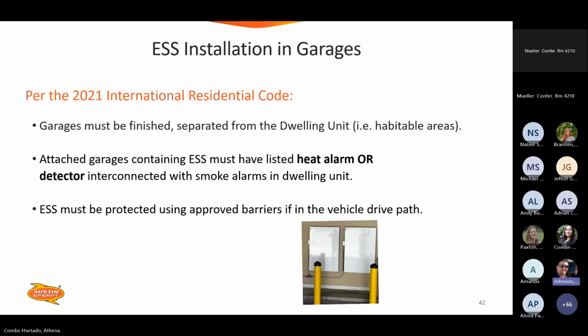Attached garages containing ESS must have a listed heat alarm or heat detector interconnected with smoke alarms in the dwelling unit. And if it is in the straightforward drive path, not on the sides of the garage, the straightforward drive path, meaning they can easily pull in and not be paying a smidgen of attention and hit the batteries, we need approved barriers, some kind of bollards, some kind of gate, some kind of protective measure so that vehicle cannot hit those batteries.